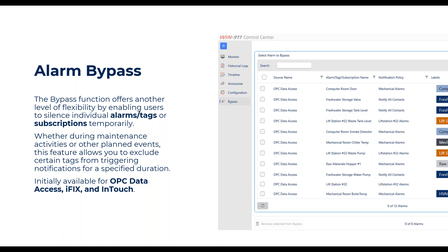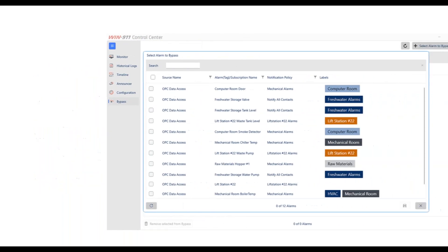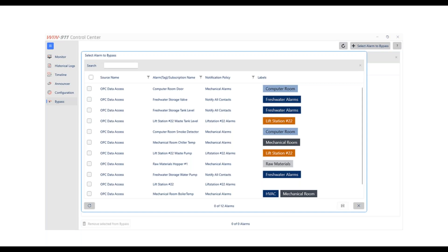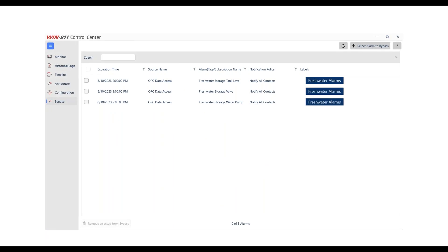There's no link to the SCADA system with suppression or anything like that — you're just bypassing it on the WIN-911 side. You get to select from a set of tags and set how long you want it to be in bypass. Those tags are bypassed until it expires or you manually remove them. When you do remove them, if the alarms are still active, WIN-911 will treat those alarms as if they're brand new and will go through escalation as if the alarm first appeared.